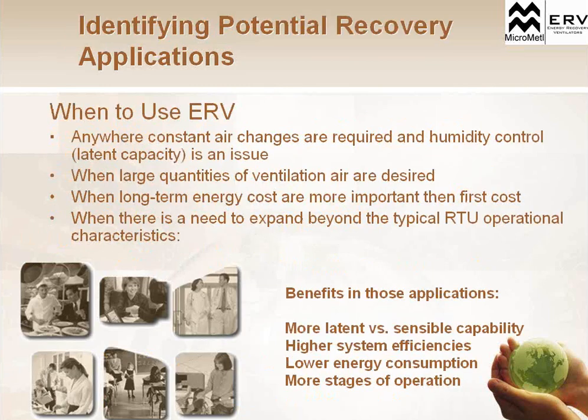So where can we use energy recovery ventilators? I've given you an introduction on where we're getting the energy savings, what an energy recovery unit does. Where do we want to use these? Where do I want to look at an application and say, I think an ERV would be a great addition to the HVAC system? Well, when you break it down, anywhere where we have large quantities of ventilation requirements, so you're bringing in a lot of outside air, either for ventilation requirements for indoor air quality, anywhere where you have consistent air changes throughout the building, and also humidity control issues. Anywhere where you have a latent capacity that's an issue during the summer and the winter is a great application for an ERV. And because an ERV does have energy savings over the life of the system, it's obviously going to be a long-term investment, whereas the first cost may not be the most appropriate. We're actually going to get the energy savings back over the life of the system.